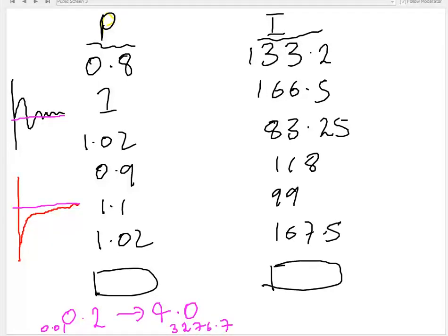Similarly with the I term, I'm making mine around about 130. That tells me it's somewhere between, say, 50 and 300. Maybe bigger than that. And once again, I've really narrowed that range down a lot. With the I term, if when you're watching it, there's the set point, and the flow is just sitting below set point and not getting there, then you know you need to give it a bit more, because the I term gives it those little nudges which get you to set point.